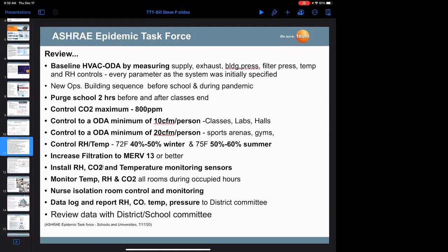Install relative humidity, CO2, and temperature monitoring sensors, we'll talk about what type to use, and measure these variables in occupied rooms on a 24-hour basis. The nursing room or nurse's location now has specific criteria to control to as well.